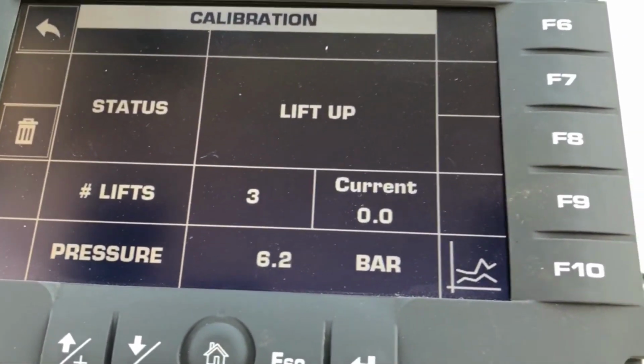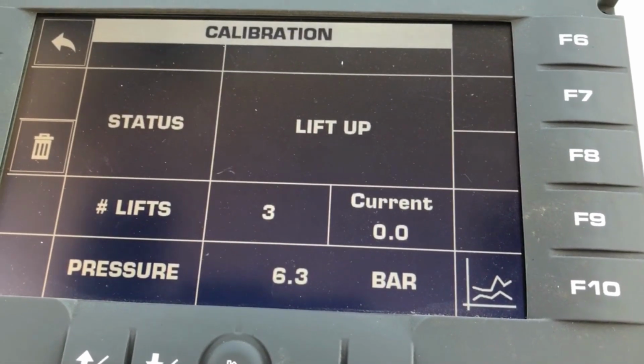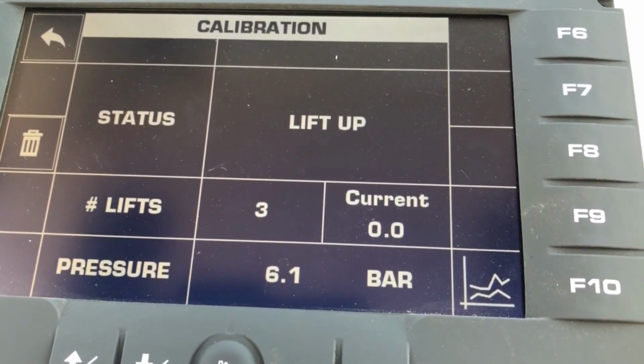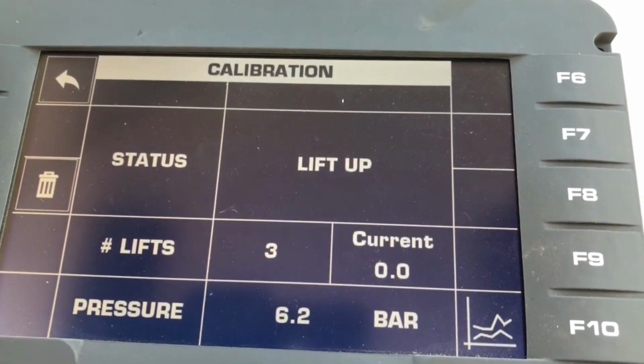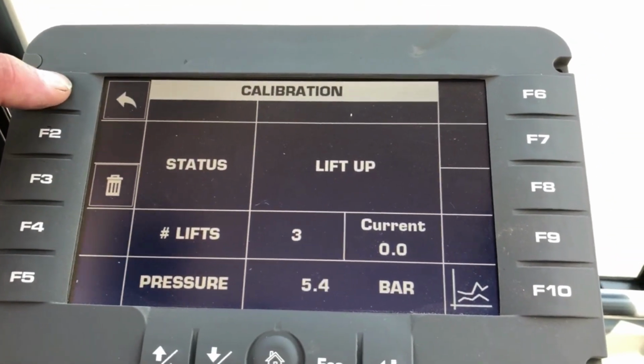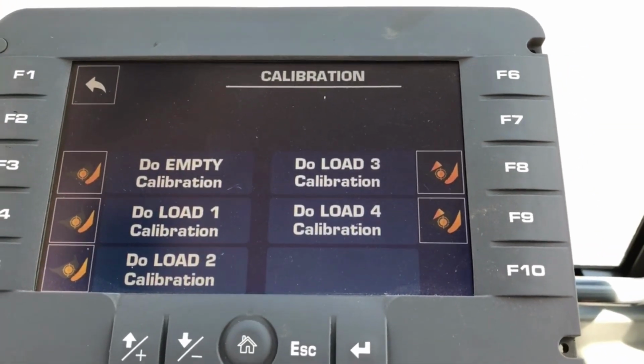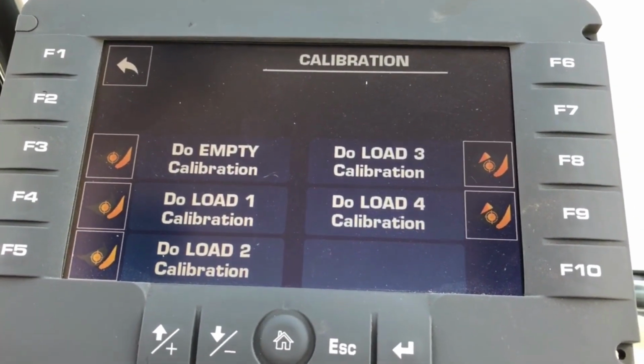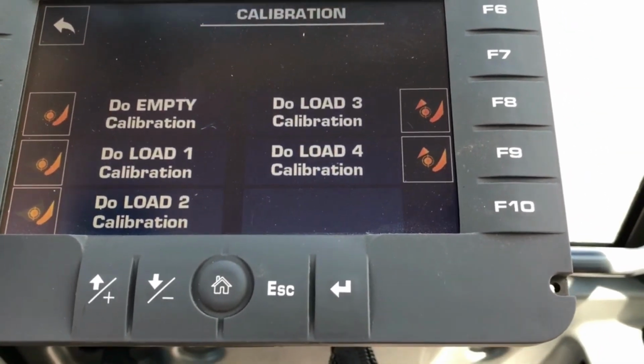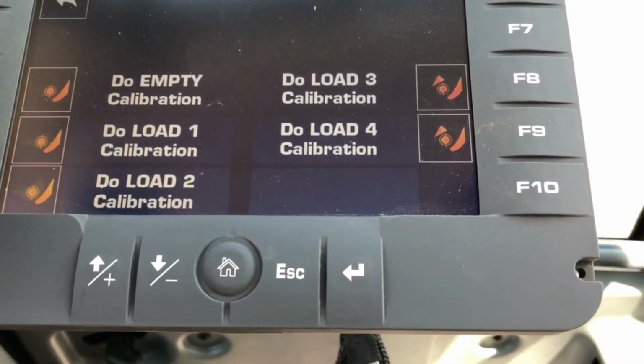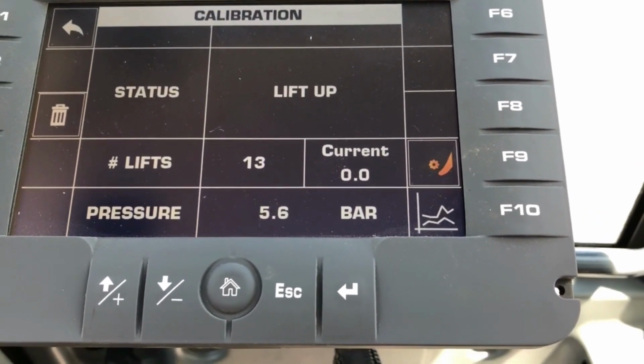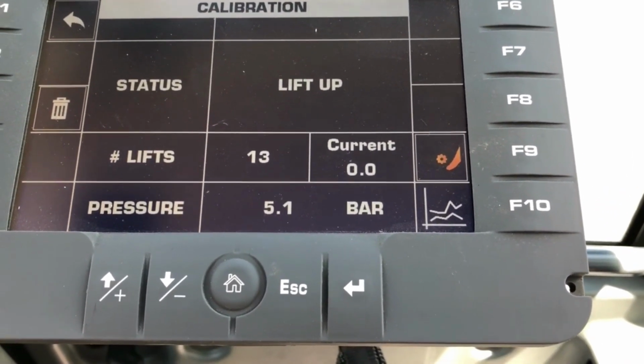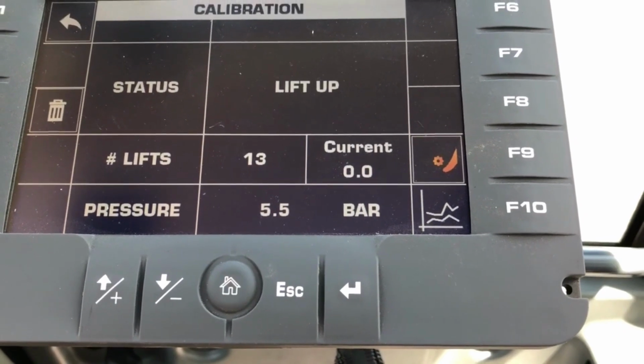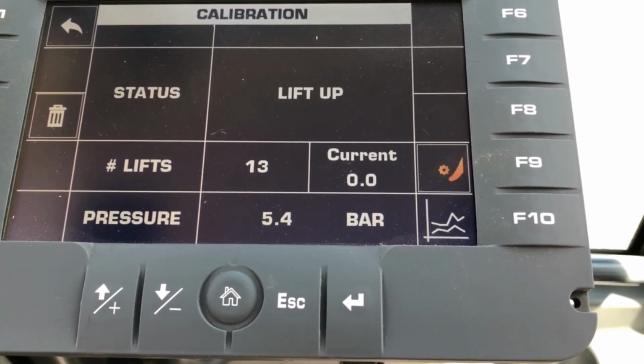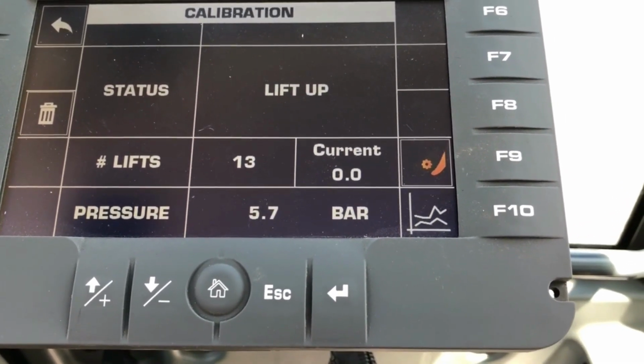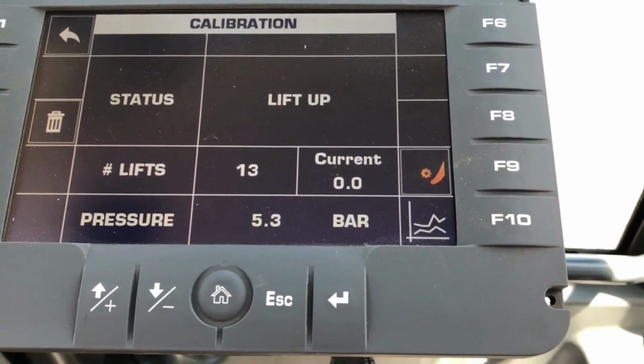Once you've done them all, say 9 or 10 or how many ever, you hit the F1 button, and then you can go into your load number 1 calibration. We're going to do the same thing there. We're going to start with a heavy or a lighter weight, and lift that at multiple speeds, starting with the faster RPM first.